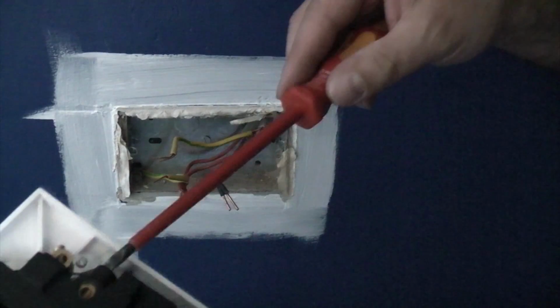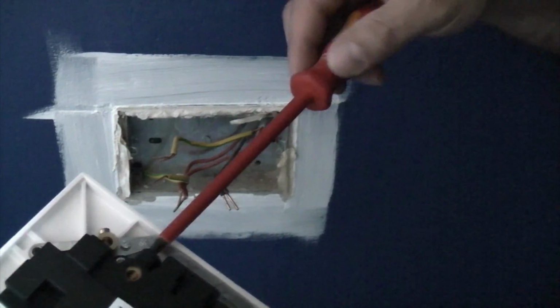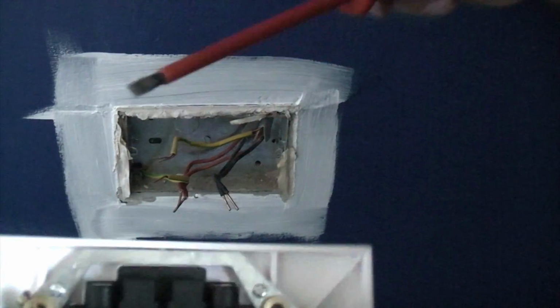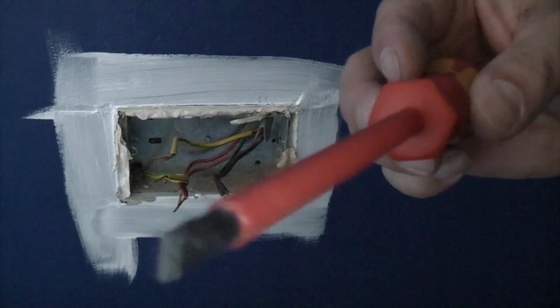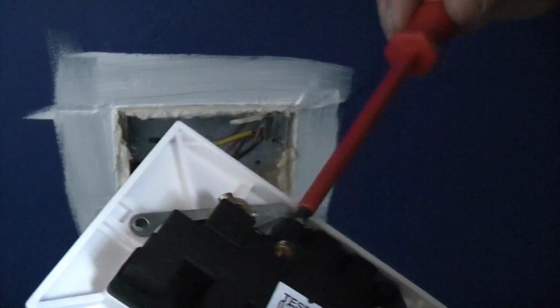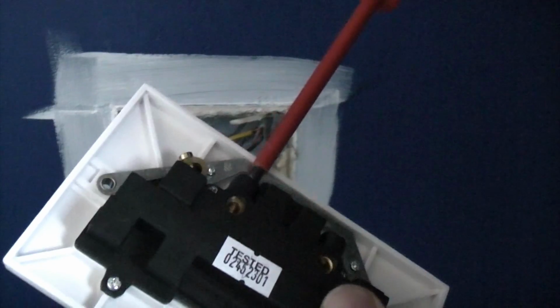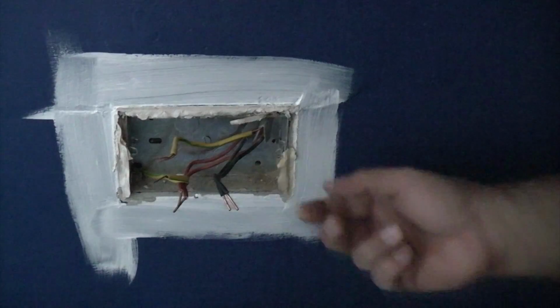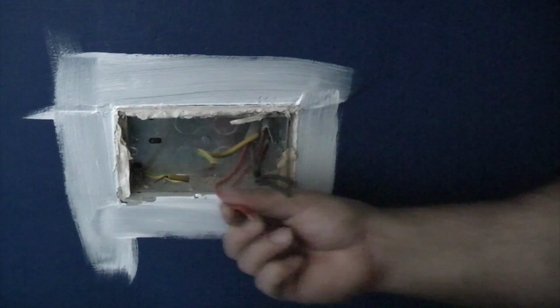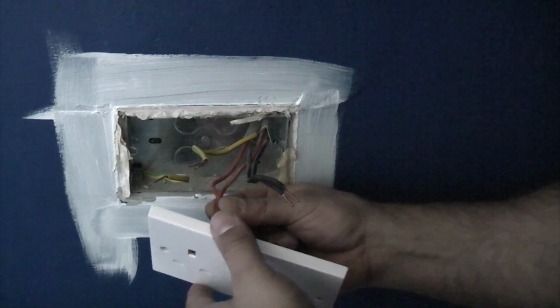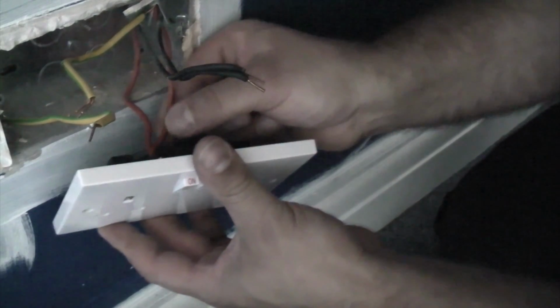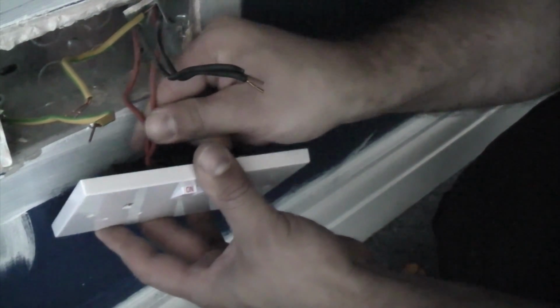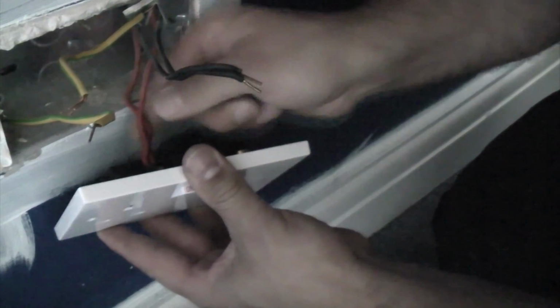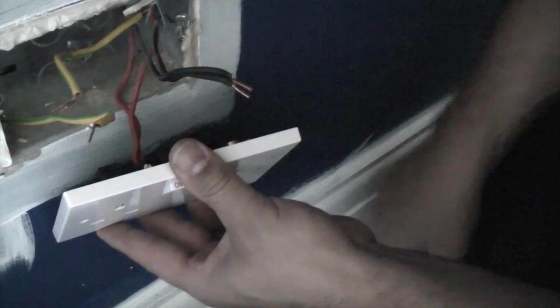So before you put it in place, it's always a good idea to undo the terminal screws. And to do this, you need a good fitting screwdriver. You don't want one that's too big or too small. So we'll start off by putting the 2 live wires in, because they're the ones that are furthest away. And when you push the cables in, it's important to get them in as far as possible so that there's no copper conductor showing.